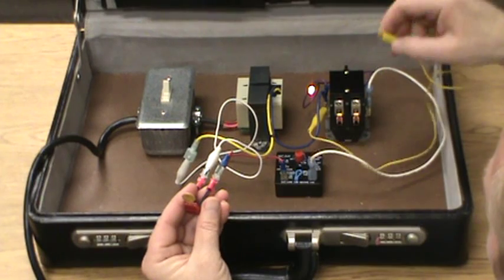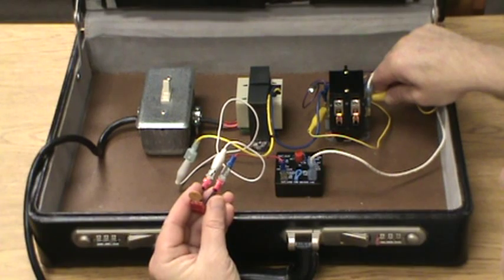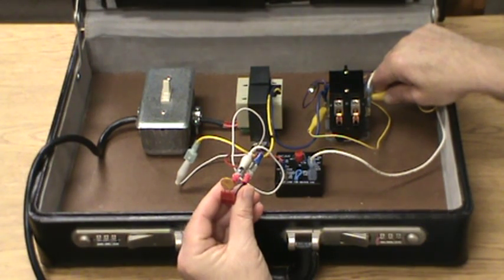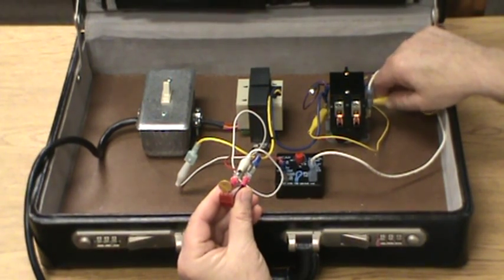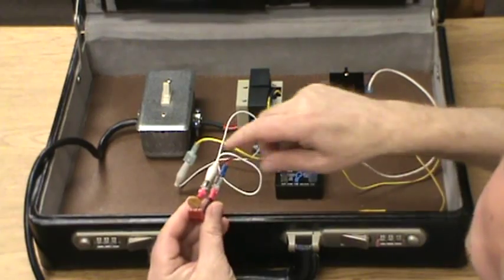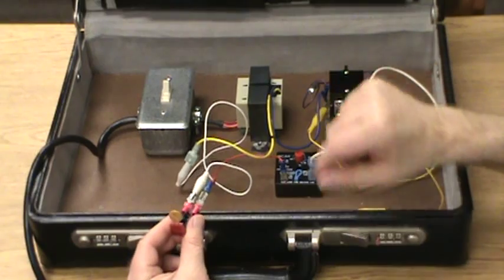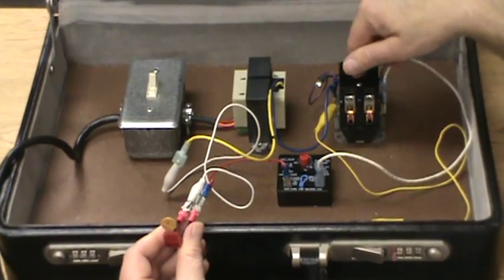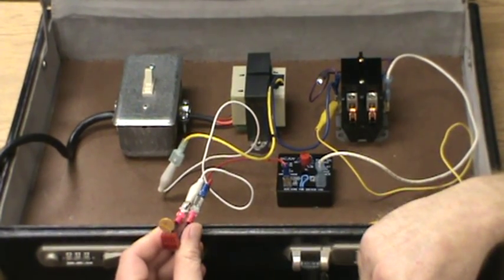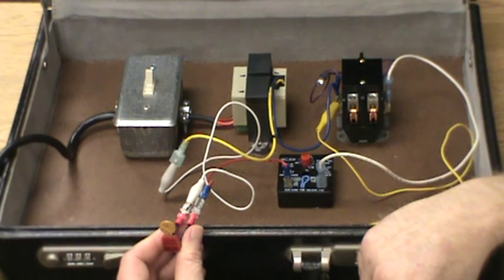Now we're going to go ahead and run a short on it. It's going to trip the resettable fuse to protect everything. I've got this short going across it right now. I'll take it off, and what it'll do is time out on this time delay. Once it's timed out, it'll reset the power and the contact will energize again. The purpose of doing this is for those intermittent shorts, so in case they happen when you're not there.